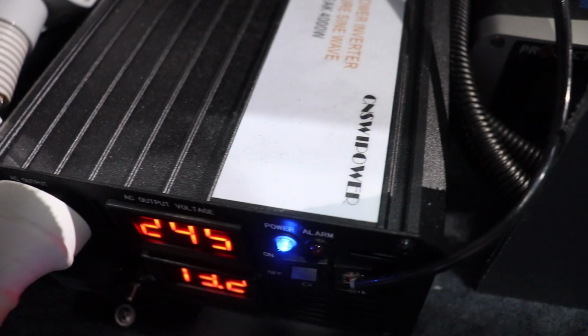Now, the other problem with rewiring all the power points to the caravan through the inverter was that the charger is also under the bed, plugged into a power point there. If I turned the inverter on and ran all the power points through it, the battery charger would come on and try to charge the batteries off the inverter, creating a really inefficient loop that would be a disaster.